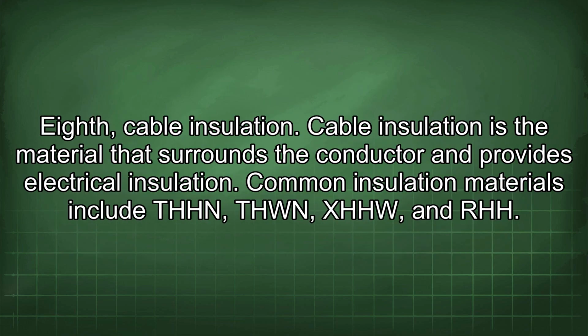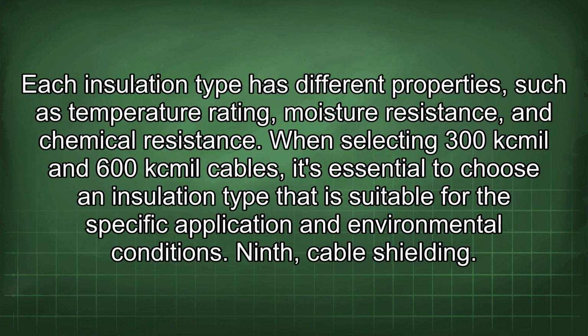Eighth, cable insulation. Cable insulation is the material that surrounds the conductor and provides electrical insulation. Common insulation materials include THHN, THWN, XHHW, and RHH. Each insulation type has different properties, such as temperature rating, moisture resistance, and chemical resistance. When selecting 300kcmil and 600kcmil cables, it's essential to choose an insulation type that is suitable for the specific application and environmental conditions. Ninth, cable shielding.